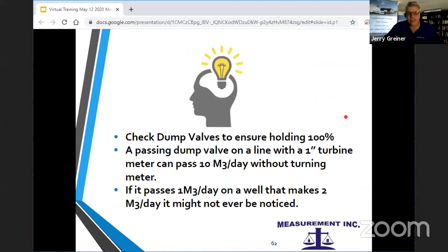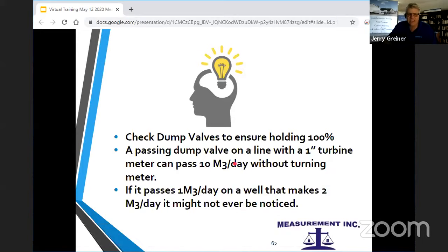And so what we need to do is check that they hold 100% of the time. A passing dump valve, if you have a 1-inch turbine meter on, needs to go about 10 cubes a day before the meter starts to turn. And so if it passes less than that, you're not going to notice it on the meter turning. And if you are not passing very much, like a 1/2 cube a day or 1 cube a day or 1/4 cube a day, as long as your well's making more than that, it doesn't lower the separator level. So it's very easy to go a long time and not get noticed.